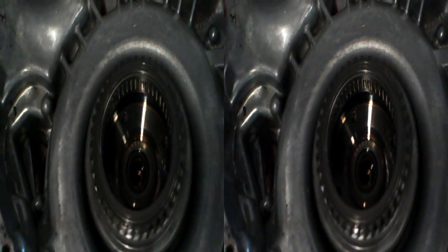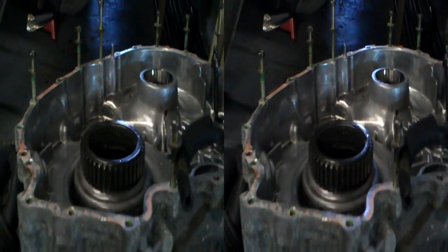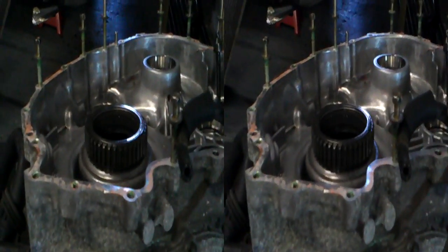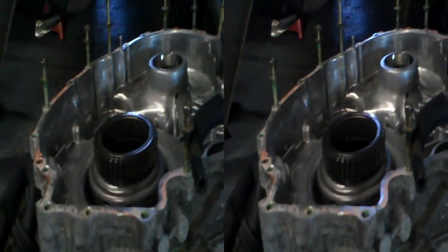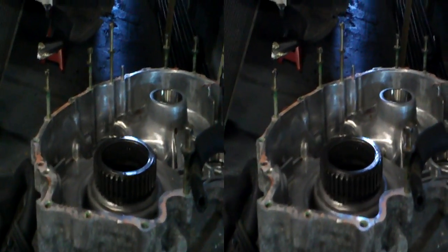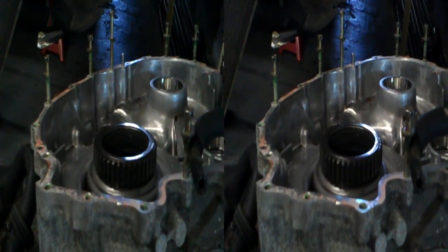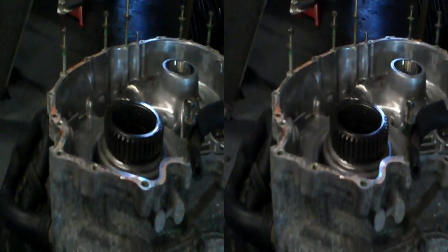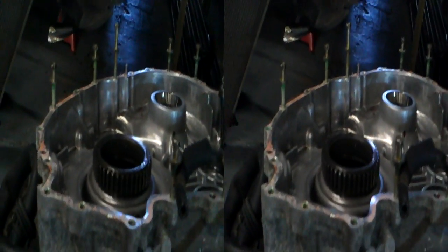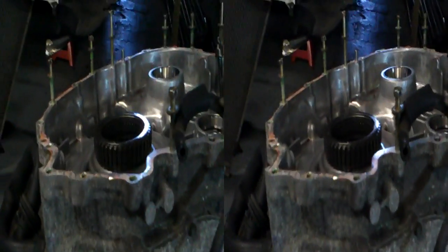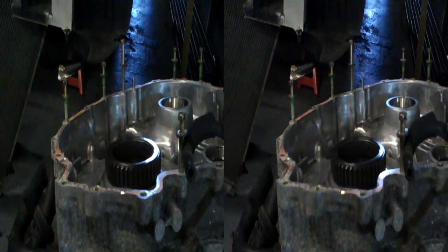Yeah. So there's your poles. See? And also, of course, we can actually lock it to find out where the absolute poles actually are. So I can do, for instance, I can lock phase A high, and then put a magnet there, sort of thing, so that I can get the synchronicity. It's quite straightforward. Or I can use the actual sensor that's on this, although I don't know where that is. So yeah, just thought I'd add that. There you go.